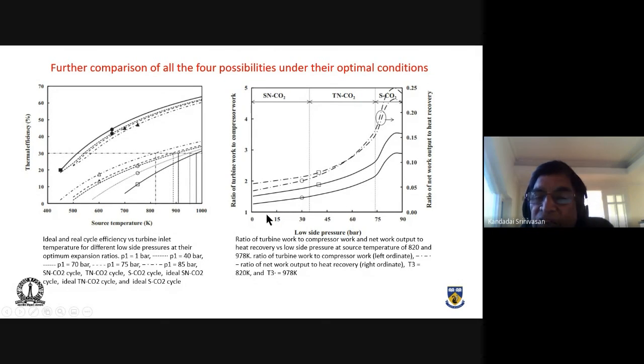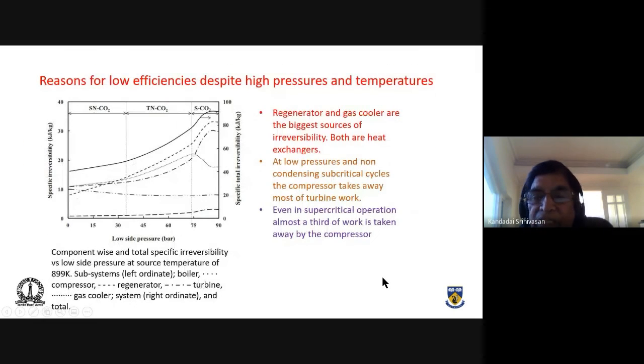This region, by and large, is not very good. It produces some power, but not very good. This is actually one of the examples of why we would like supercritical carbon dioxide power generation. They confirm the efficiency is almost comparable to that of the steam cycle. The turbine work to compressor work ratio is much better, pretty close, it goes up to about 3. The heat recovery ratio is also quite large in this case. That's obvious: the more the heat recovery ratio, the less will be the compressor work, so less will be this ratio also. That gels very well. Now let's see the next one.